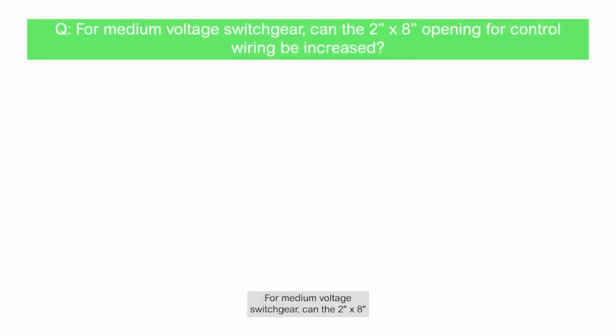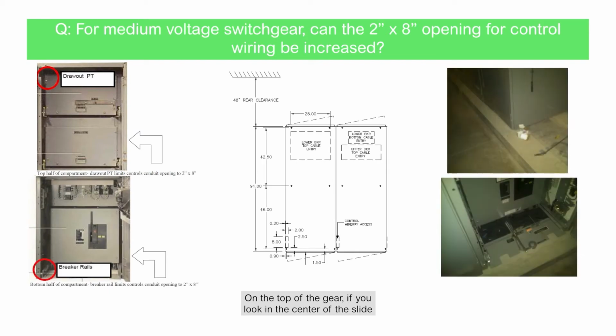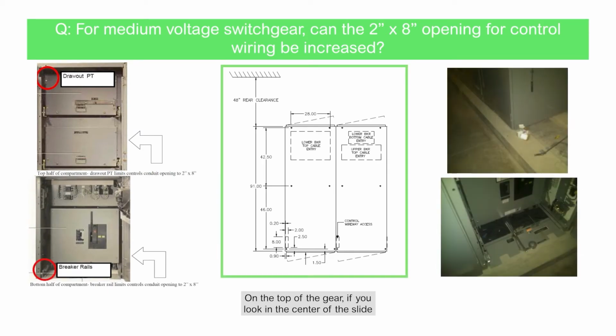For medium voltage switchgear, can the 2 by 8 inches opening for control wire be increased? On the top of the gear, if you look in the center of the slide there, you'll see there's a little 2 by 8 inches opening which is designated just for the control wiring to the applicable section of medium voltage switchgear. The answer is that the 2 by 8 inches opening cannot be expanded any larger.